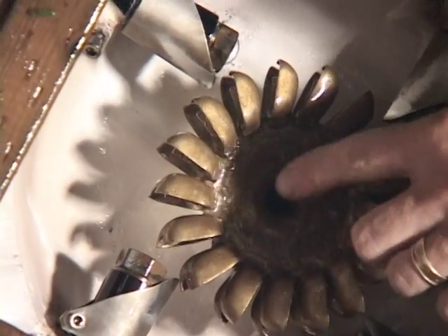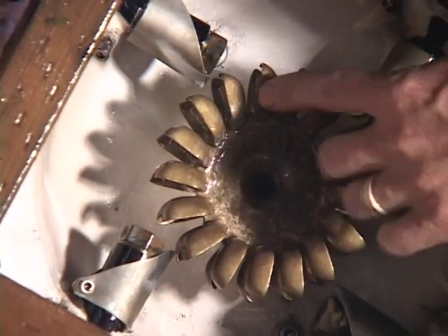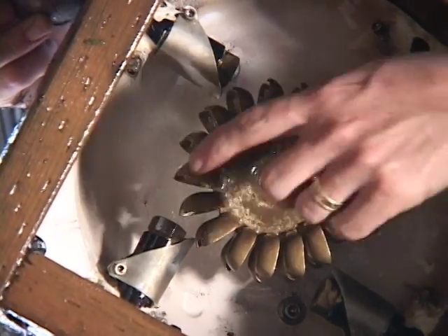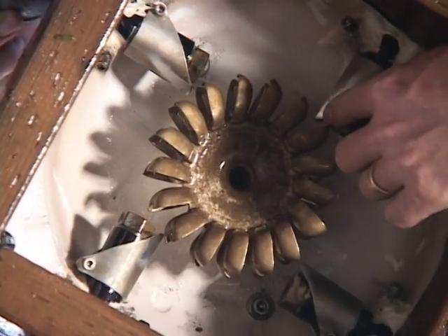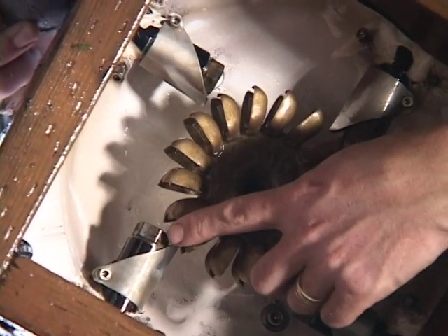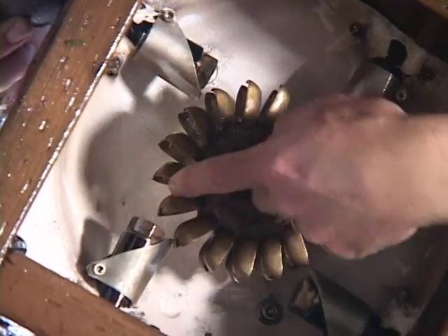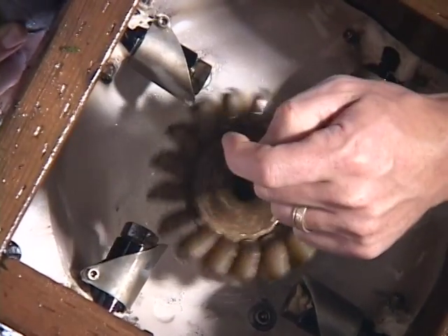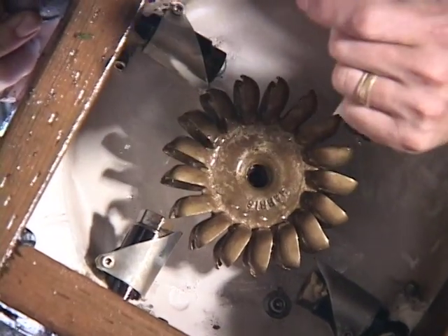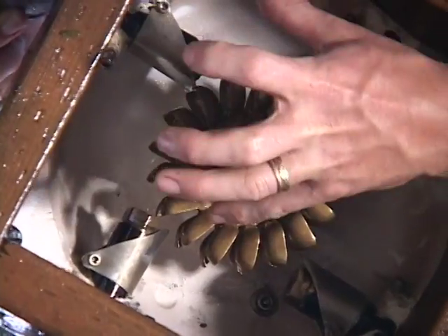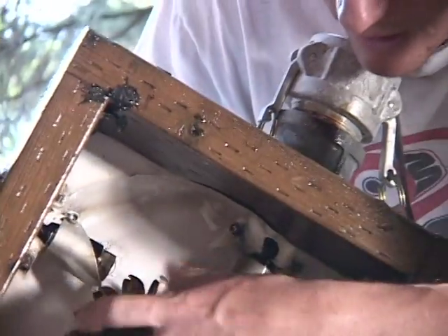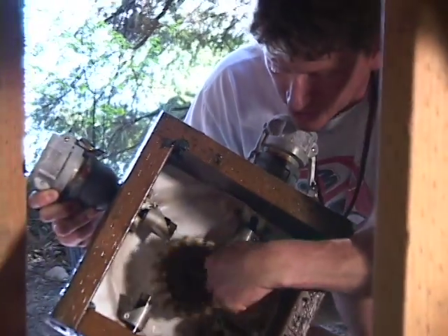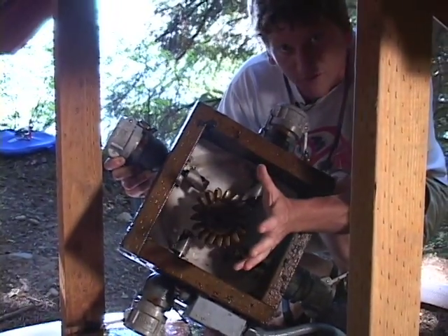This is a cast bronze Pelton wheel that's attached to the shaft of the alternator to directly drive it. There are 4 jets or nozzles that shoot water under pressure into the cups of the runner and spin the alternator. This is designed to take the maximum amount of energy available from the water and turn it into rotational energy.